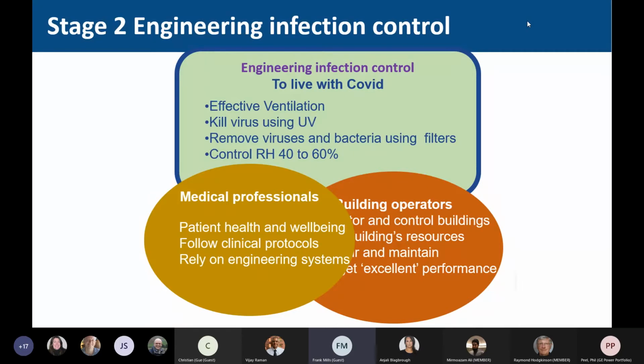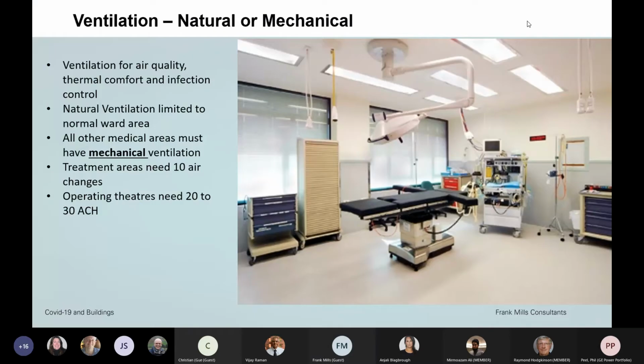But we as engineers sit at the top there, and we can introduce effective ventilation. We can use UV, ultraviolet light, to kill any bacteria or viruses in the air. And then we could use filtration, usually HEPA filtration or a good standard of filter, maybe an F7, which can remove these particles and hold them in the filter. At some point, that filter can be removed and disposed of as a biohazard, then replaced with a new one. There's also some evidence that controlling relative humidity is another way of reducing the risk of viral spread, although that's not commonly used at the moment.